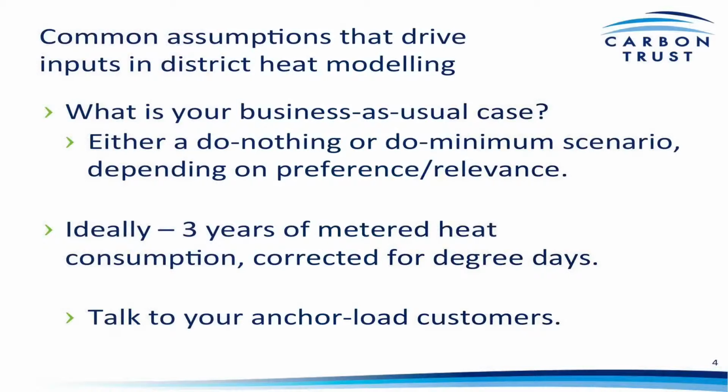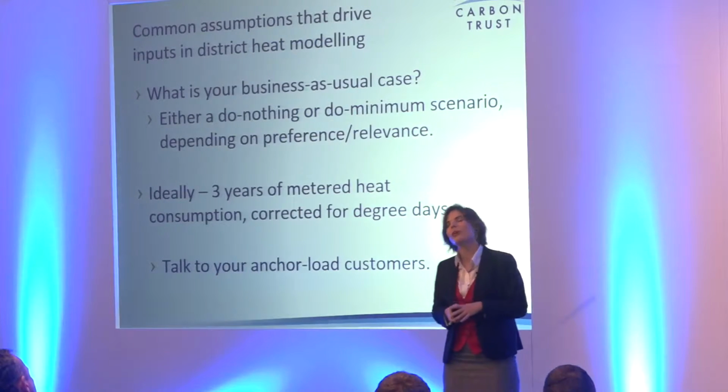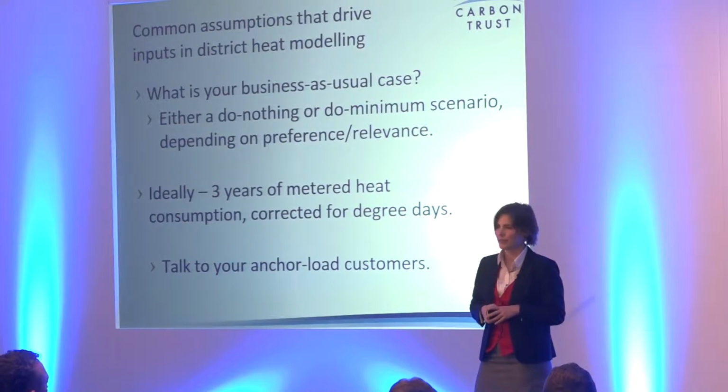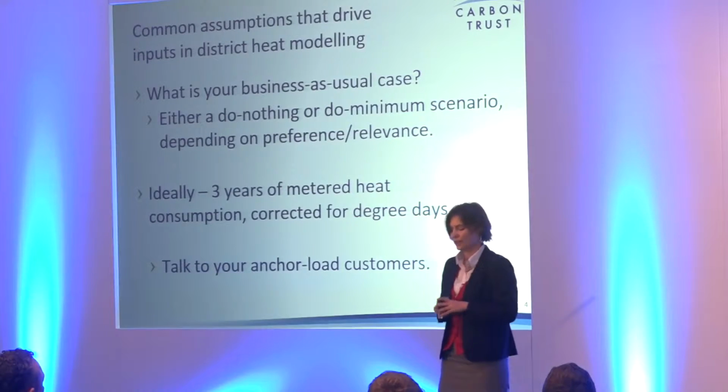To start with, common assumptions. The key one, if you're building a district heat business model, is to know your business as usual case. And that will be either a do nothing or do minimum, or in some cases it will be both. And I've written ideally, but actually, as a minimum, you should have at least 3 years knowledge of the kind of heat consumption your customer base has. Now, in cases where you're doing new build, obviously that's not always a possibility, but there you should do some reality check on what other new builds are doing across the country and what kind of heat consumption they have, because some of the standard assumptions tend to overstate heat demand.